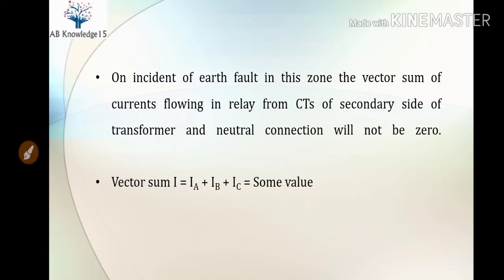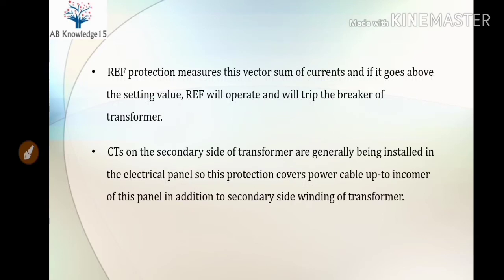On the incident of an earth fault in this zone, the vector sum of currents flowing in the relay from the CTs of the secondary side and the neutral connection will no longer be zero. The vector sum I equals Ia plus Ib plus Ic will have some non-zero value. Upon this value, the relay of REF protection will sense that there is an earth fault in the zone. REF protection measures this vector sum of currents, and if it goes above the setting value, REF will operate and trip the breaker of the transformer.